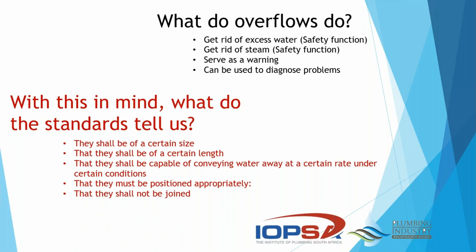Then they shall not be joined. You cannot join a TP with a PRV, or put a PRV into a tray, or a TP into a tray, or something like that. Again, it's got to do with safety. It's got to do with visibility and as a diagnostic tool. And they should not be a risk or a nuisance. So if it's going to be risky to person or property, or a nuisance, then it's a no-go.